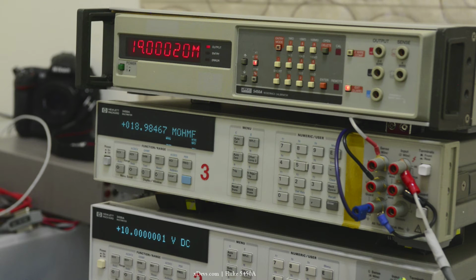That's also one of the reasons why I always prefer to run the remote control over GPIB. So I can set up the program to collect the data and the instrument runs and does its work, and I just go to sleep, and then in the morning I'll see the collected data instead of writing down each reading and waiting tremendous amounts of time. And because of the age of these instruments, there is no modern USB or Ethernet or similar interfaces, not even RS-232. So the only way to communicate with this is using the GPIB interface.